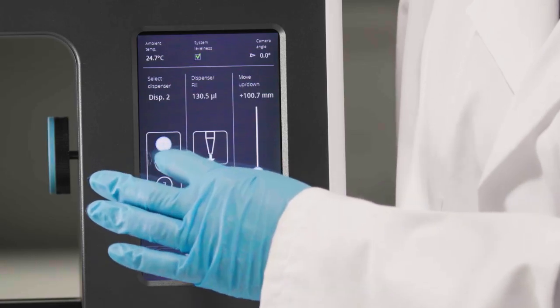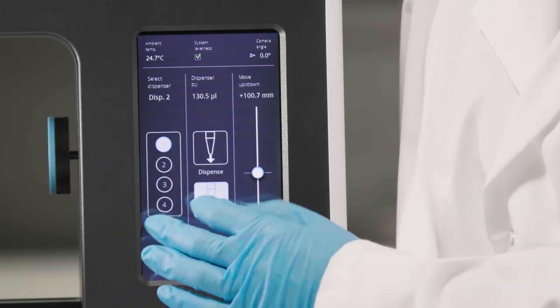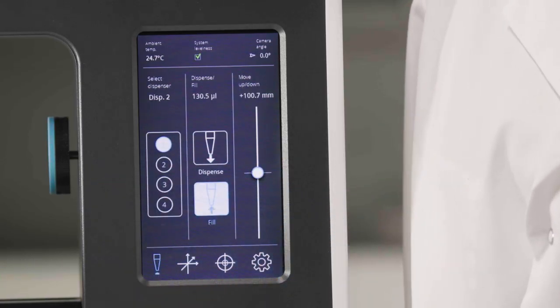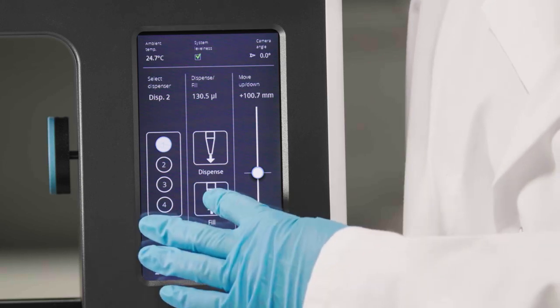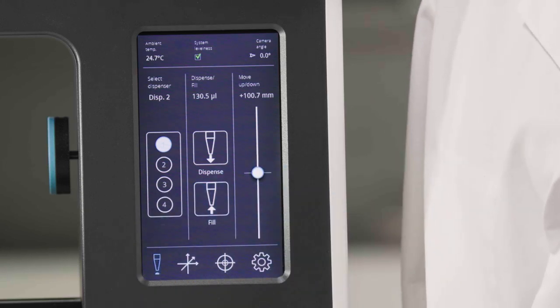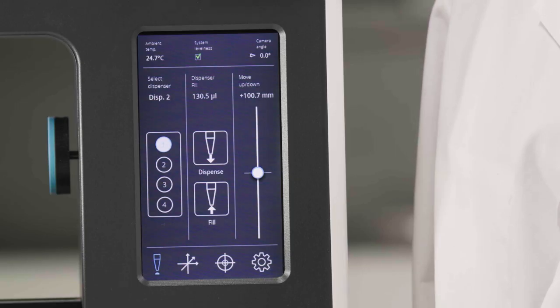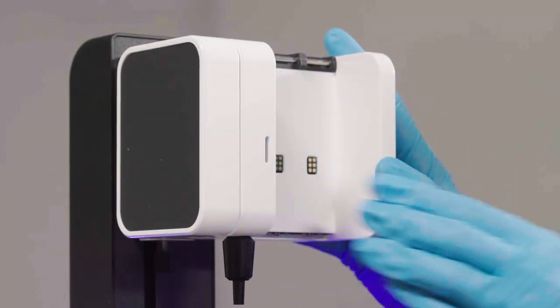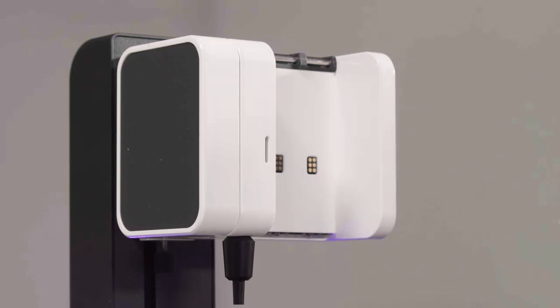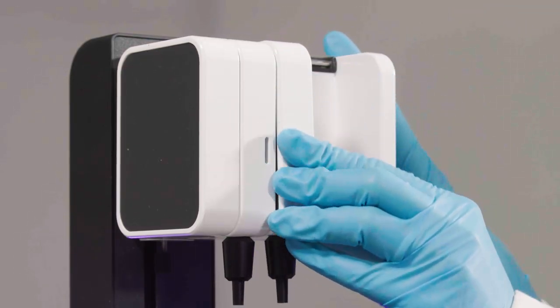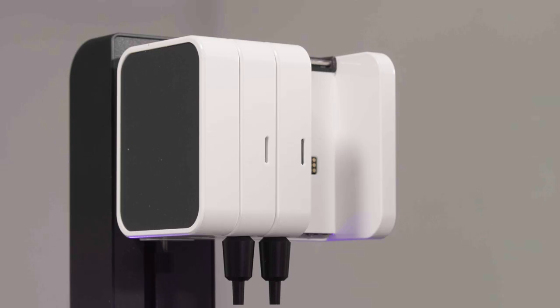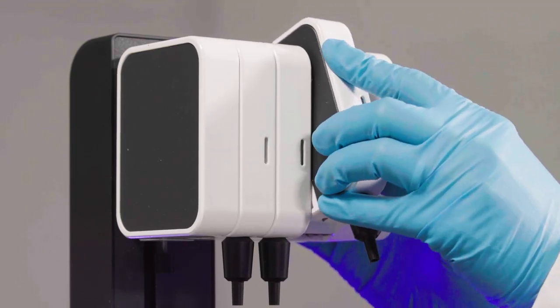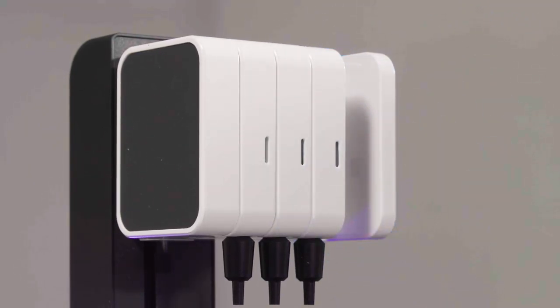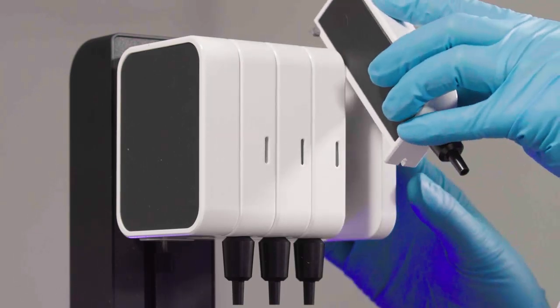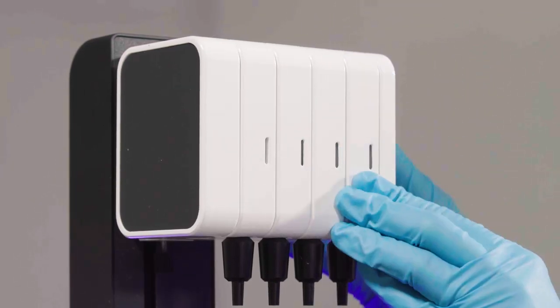The touchscreen of Theta Flow makes setting up the measurement easy as all the automated functions can be controlled directly from the instrument. You can fill and empty the dispenser easily, as well as position your sample under the dispenser. In Theta Flow, you can have up to 4 disposable tip dispensers connected at the same time. Disposable tip dispensers are convenient as they allow you to quickly change from one liquid to another without the need for cleaning. It is also possible to make small drops with the same dispenser, as will be demonstrated later.